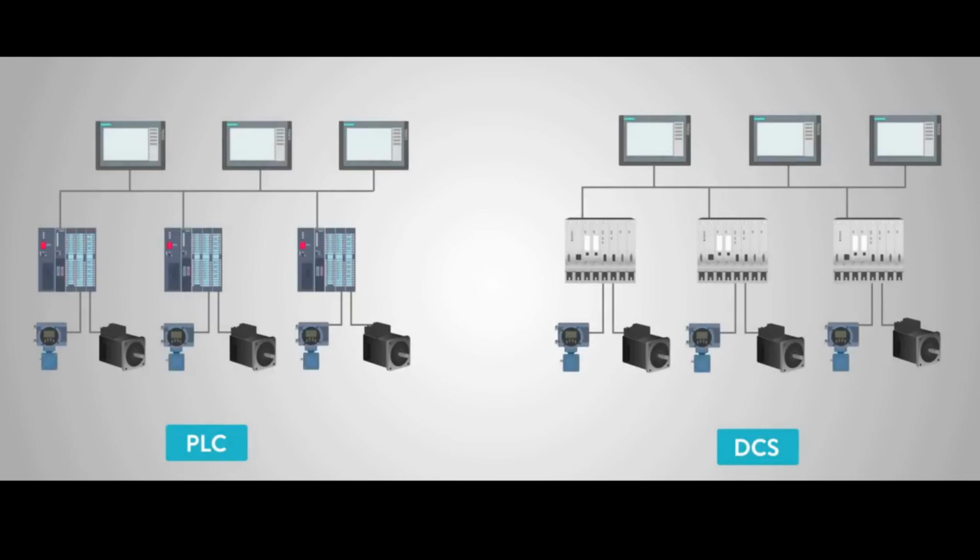In speaking of advantages, today's PLC systems can have nearly the same as the DCS, excluding the supervisory control and data acquisition, or SCADA. With a PLC system, multiple PLCs in a plant structure, you still need to create the supervisory and control system. The entire DCS database would be available for the creation of the monitoring system. The PLC system's individual PLC databases would need to be created in the SCADA system software.